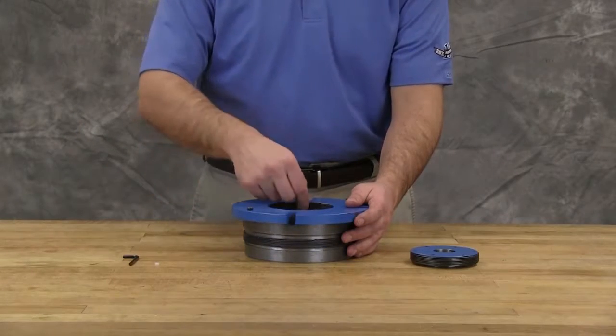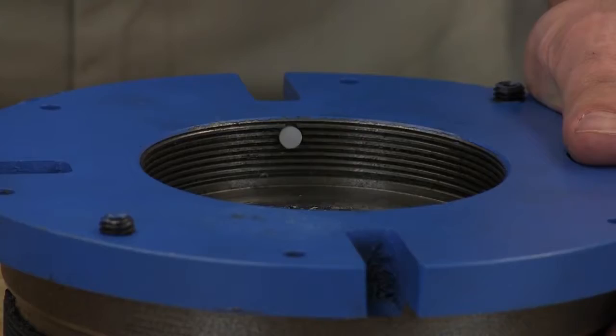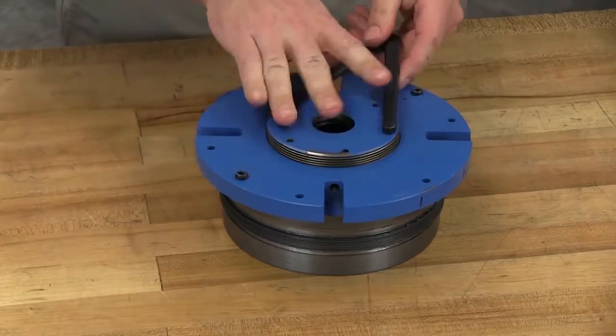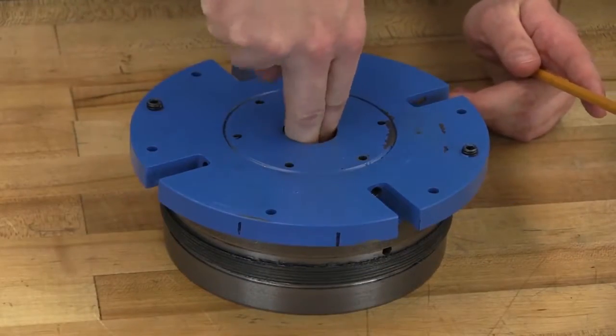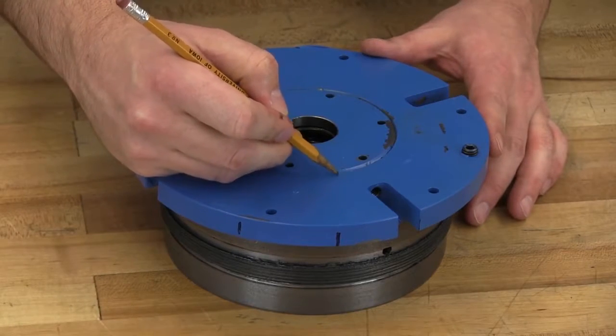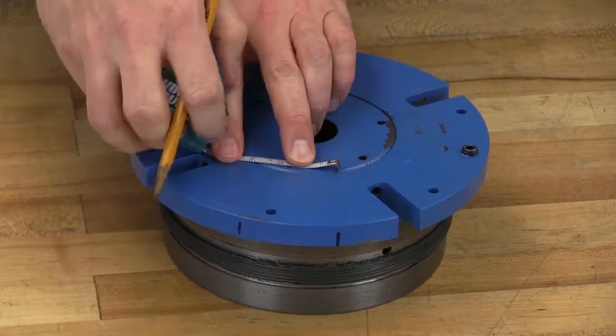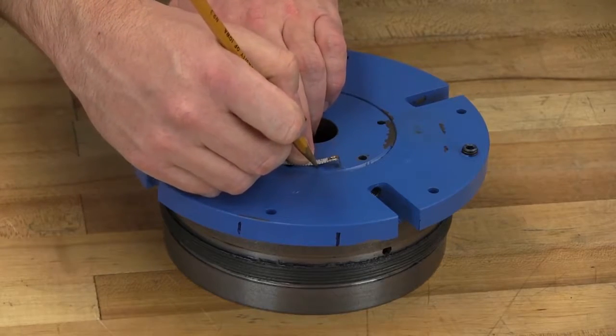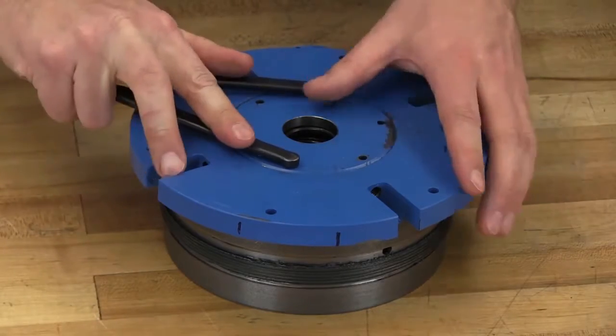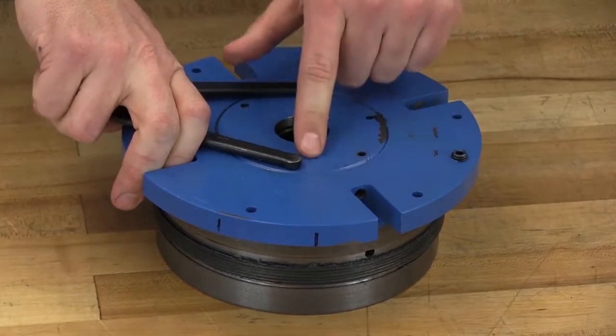Insert two nylon plugs into the holes on the threads of the bearing end cap. Install and turn the outer end cap into the bearing housing until it is tight against the inner races of the bearing and they cannot be rotated by hand. Make a mark on the outside diameter of the bearing housing and a corresponding mark on the bearing housing end cap. Measure five sixteenths of an inch and make another mark on the bearing housing. Rotate the bearing housing end cap in a counter-clockwise direction until the mark on the outside diameter of the bearing housing aligns with the measured mark. This will provide the correct end play for the bearings.